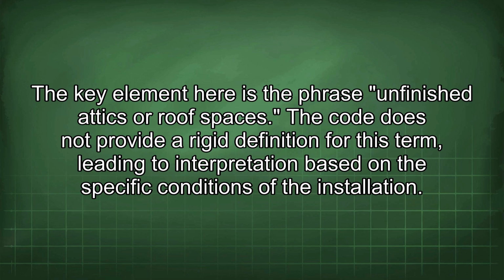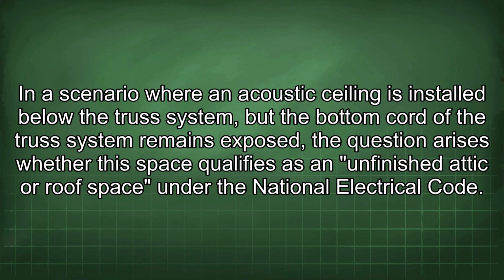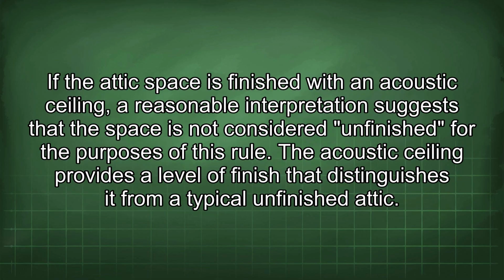The code does not provide a rigid definition for this term, leading to interpretation based on the specific conditions of the installation. In a scenario where an acoustic ceiling is installed below the truss system, but the bottom chord of the truss system remains exposed, the question arises whether the space qualifies as an unfinished attic or roof space under the National Electrical Code. If the attic space is finished with an acoustic ceiling, a reasonable interpretation suggests that the space is not considered unfinished for the purposes of this rule.